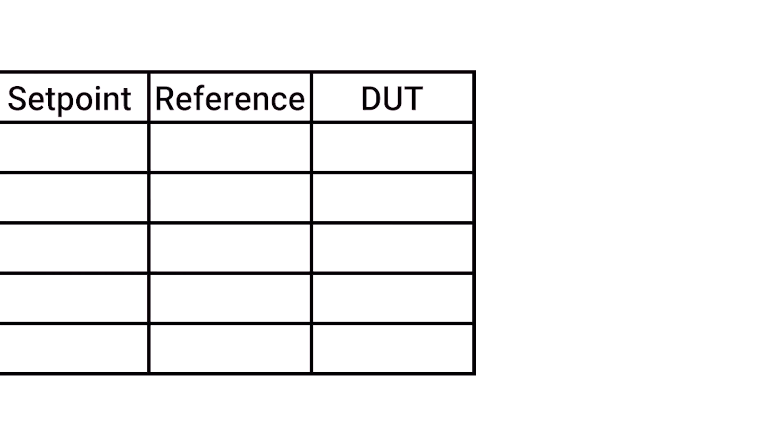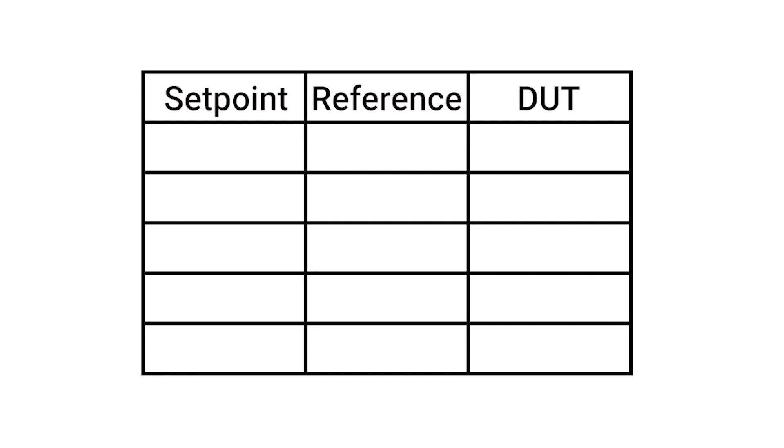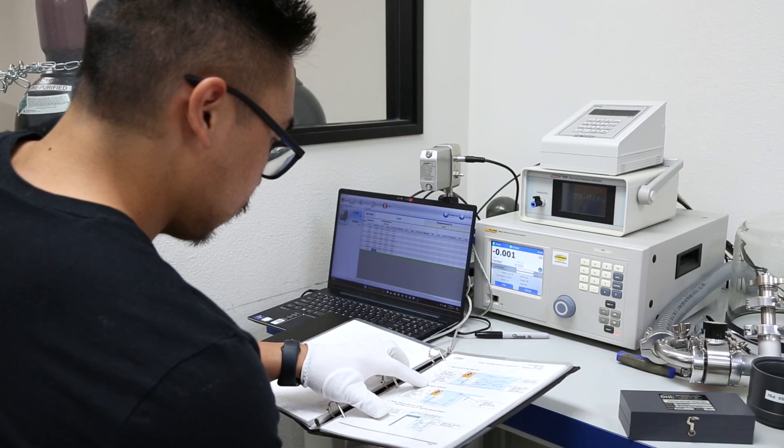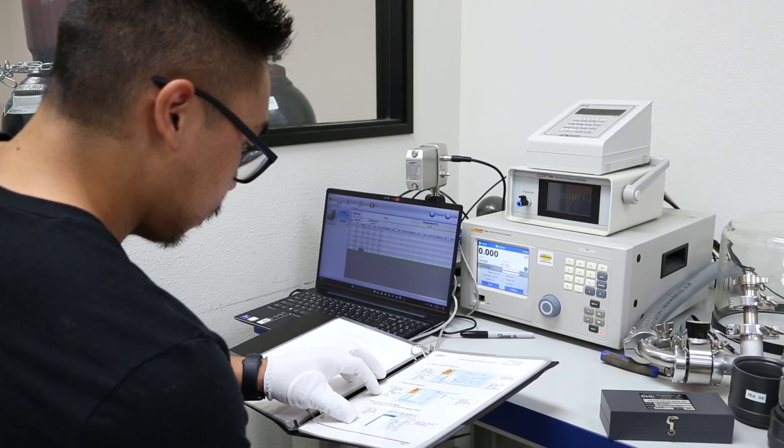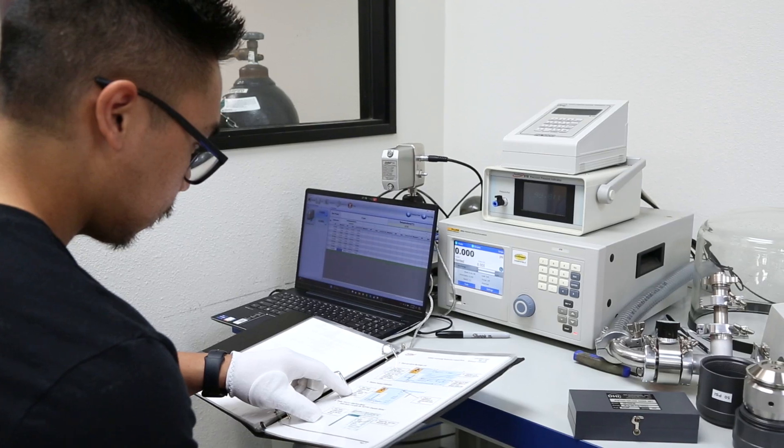Now, choose your set points for comparison. For simplicity's sake, we will do a 5-point round-trip calibration, with set points at 0, 150, 300, 150, and 0 psi. Your company or governing body should have written standards that determine the amount of set points you will use in your own calibrations.